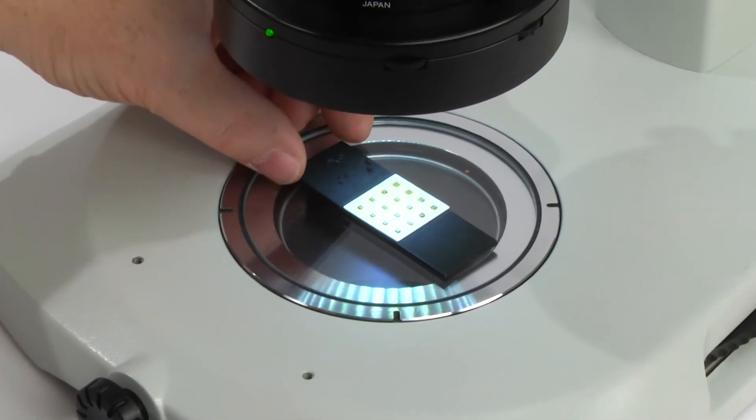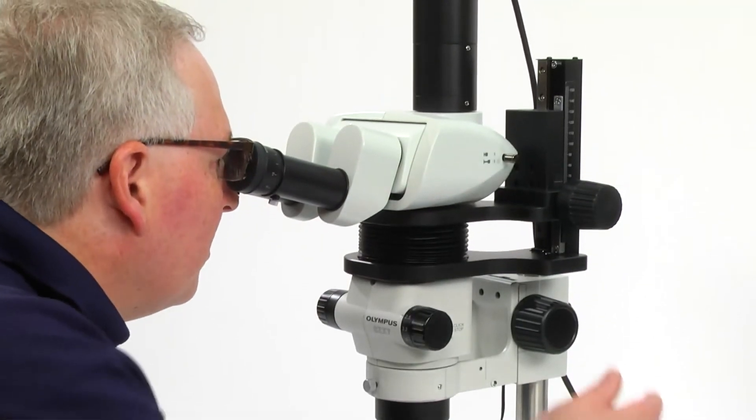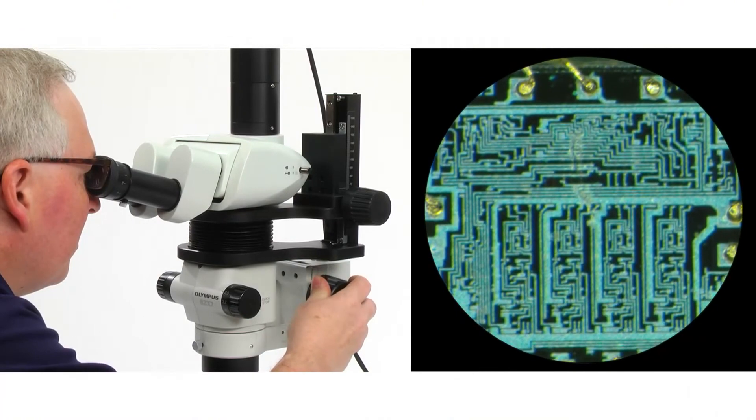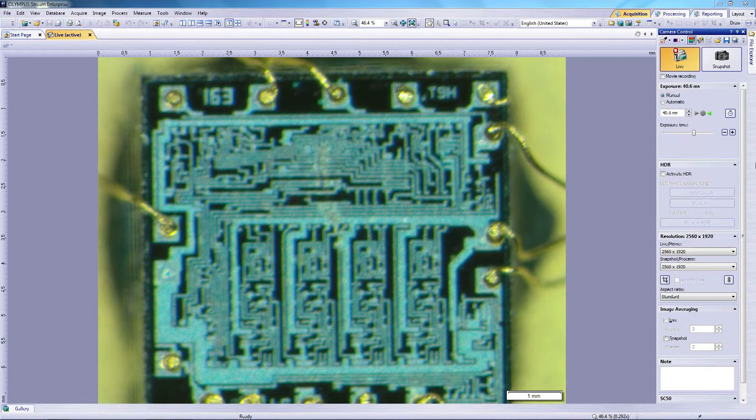First, place a sample on the stage plate. While looking through the eyepieces, bring the image into focus using the microscope focus knob. Display the image on the monitor. If the image on the monitor screen is blurry, a parfocality adjustment is required.